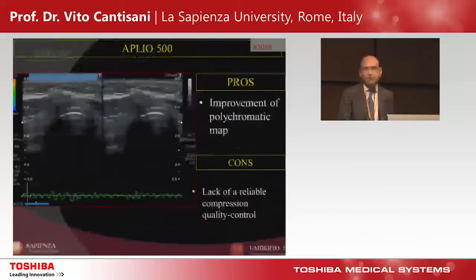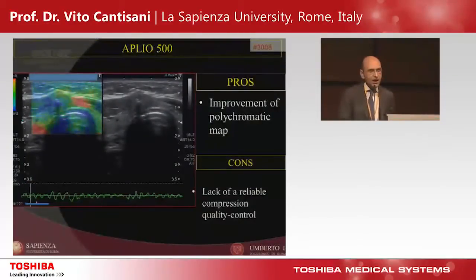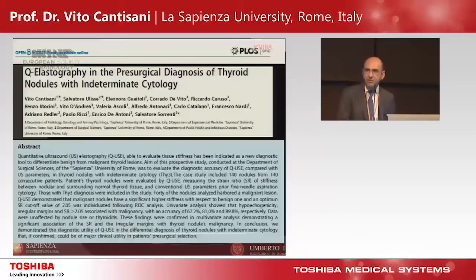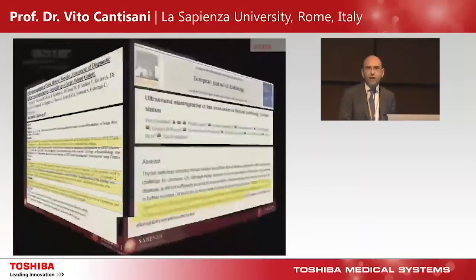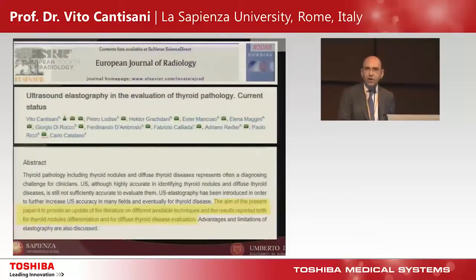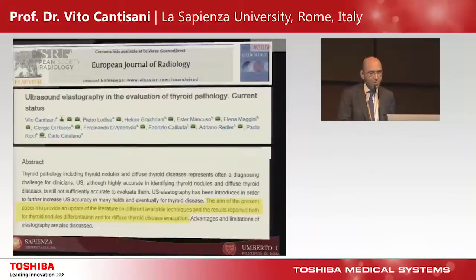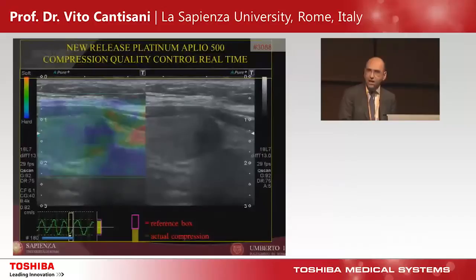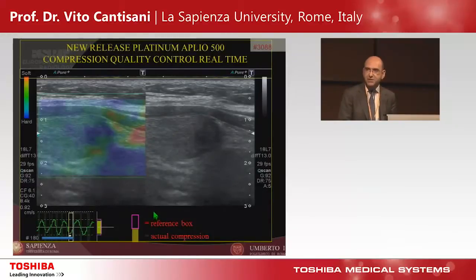After that, we had the possibility to use refinements of the technology, obtaining new software which gave us more reliable compression and more beautiful images. We continued our experience evaluating TI-RADS 3 indeterminate nodules and inter-observer variability, finding that ultrasound elastography reduced inter-observer variability. However, strain elastography remains operator-dependent, so to reduce variability in compression we need real-time compression quality control, which the new platinum series equipment provides, based on compression intensity and duration.